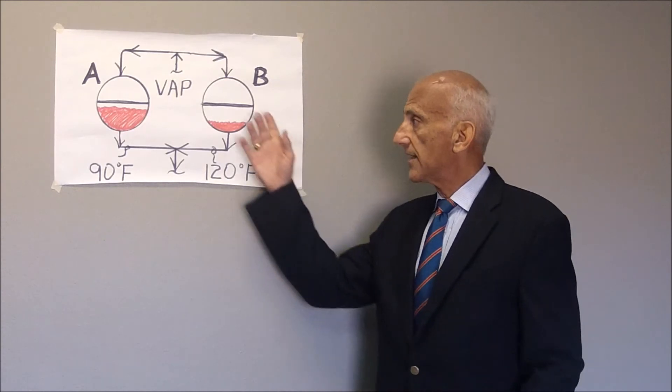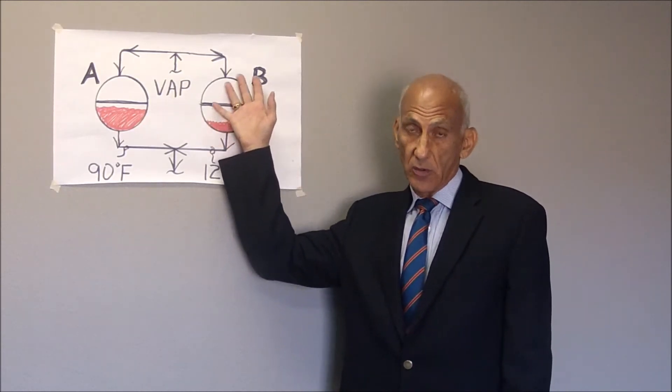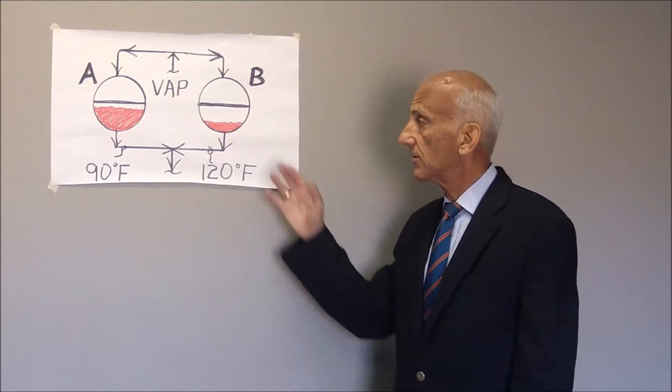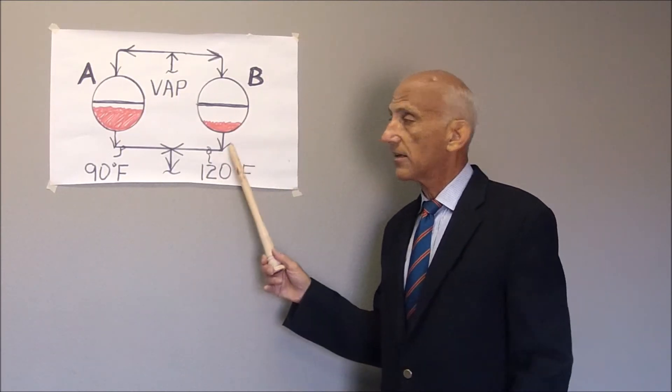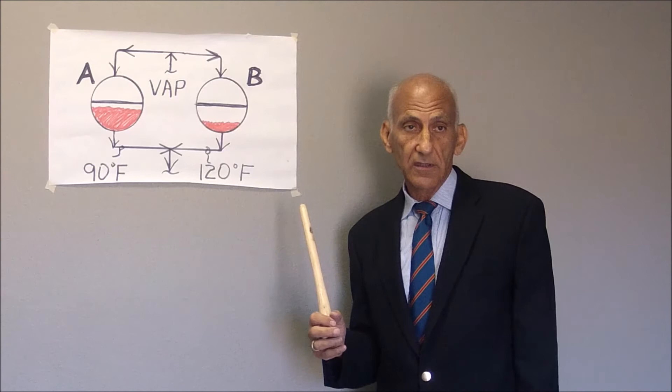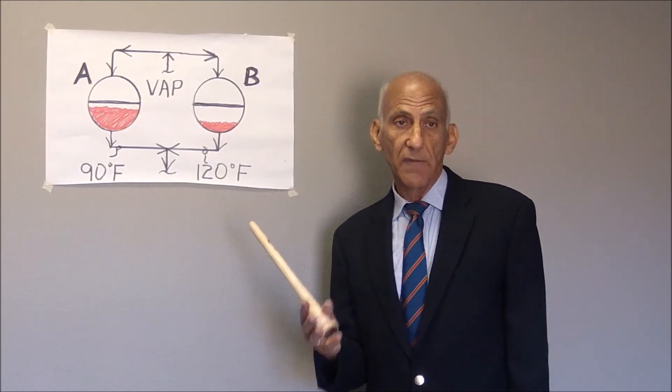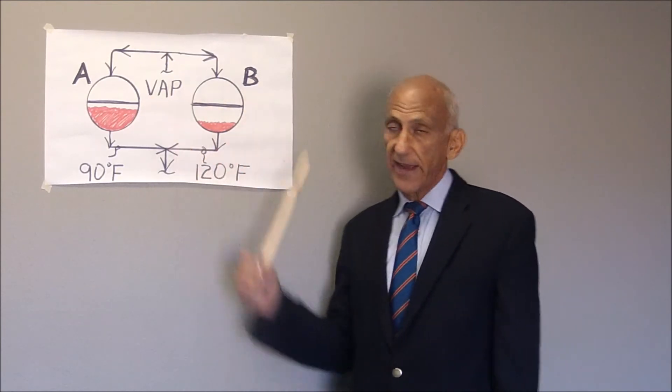So the condenser duty of B will go up, and it will have a tendency to develop a higher condenser outlet temperature. Well, primarily because it's doing a bigger load of condensation than condenser A.